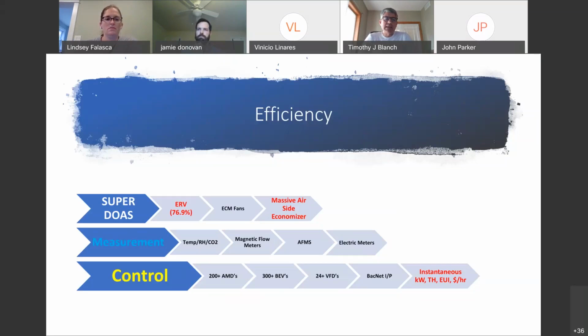That was something we hadn't done before. We put magnetic flow meters in, not turbine style, which get gummed up under recorded waste energy. AFMS, airflow measuring stations. That is a damper combined with a flow meter so that you can measure how many CFMs are going in through the device and then modulate it.